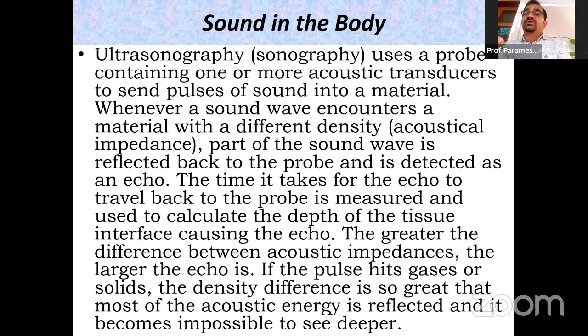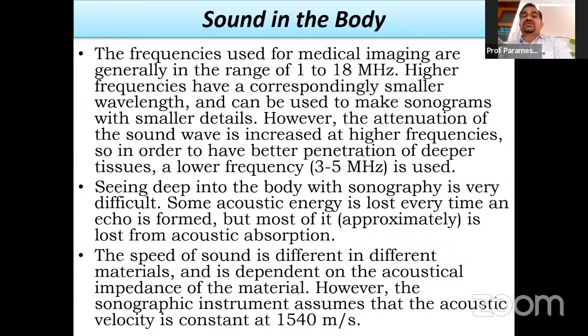The frequencies used for medical imaging are generally between 1 and 18 megahertz, but higher frequencies correspond to smaller wavelengths and can be used to make sonograms with smaller details. However, the attenuation of the sound wave increases at higher frequencies. So in order to have better penetration of deeper tissues, a lower frequency, 3 to 5 megahertz, is used. Seeing deep into the body with sonography is very difficult. Some acoustic energy is lost every time an echo is formed, but most of it is lost through acoustic absorption. The speed of sound is different in different materials and depends on the acoustic impedance of the material, but the sonographic instrument assumes that the acoustic velocity is a constant 1540 meters per second.